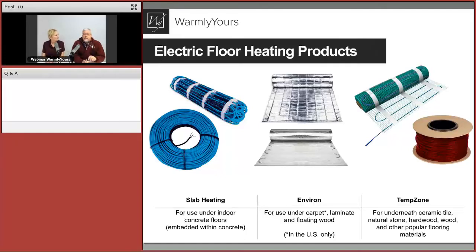The cable lets you get into areas that are rounded or oblong, different sizes and shapes, because you can do it as you're out there. Otherwise, you'd have to do a lot of cuts and turns of the mesh. But if I know I'm going to be doing a big rectangular space, give me the rolls all day long, because I just roll them out, cut them and turn them. I'm always cutting the mesh, never the cable, and then I can lay out hundreds of square feet much, much quicker than doing the loose cable. Excellent. So new construction additions.